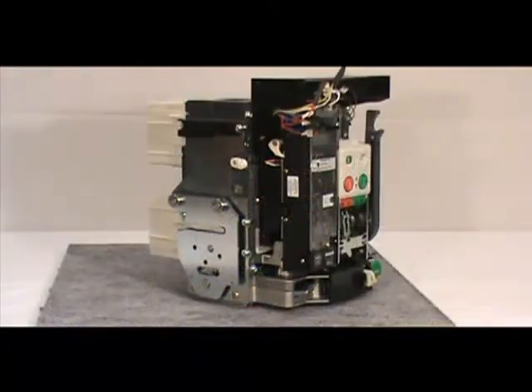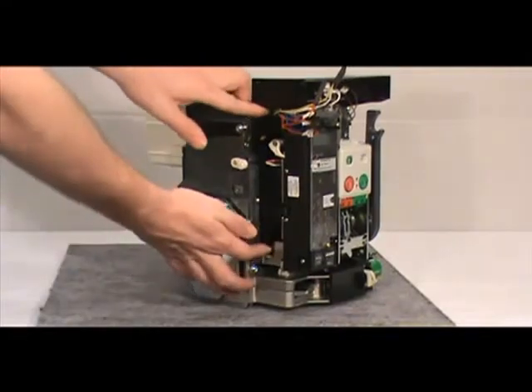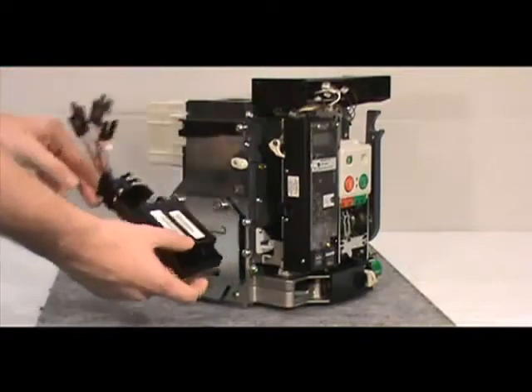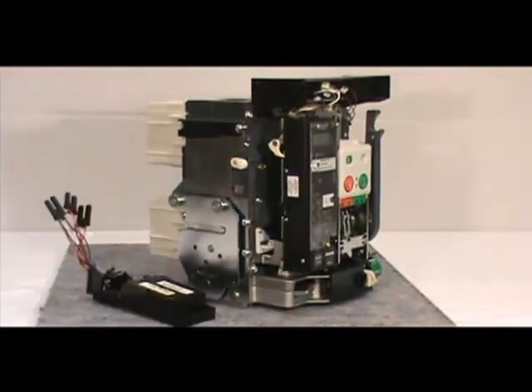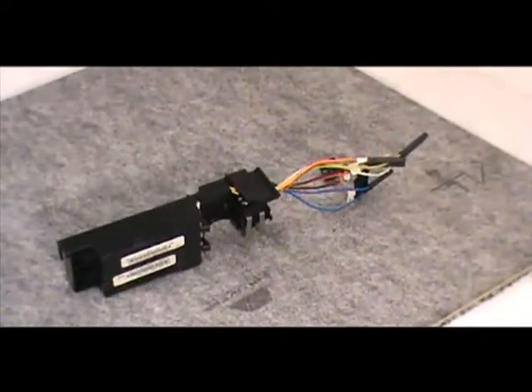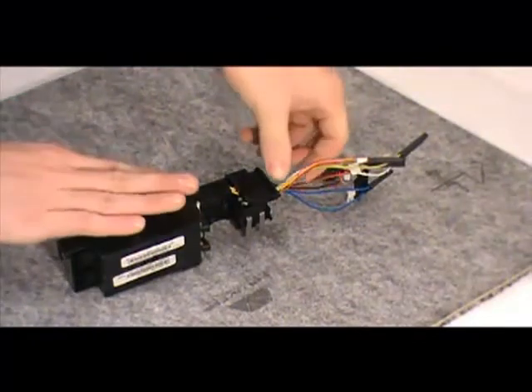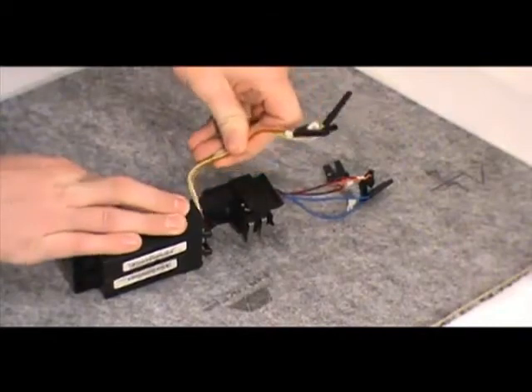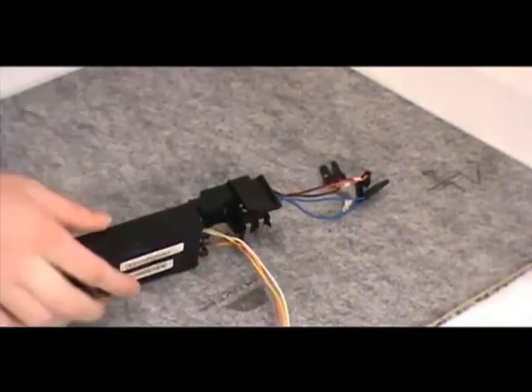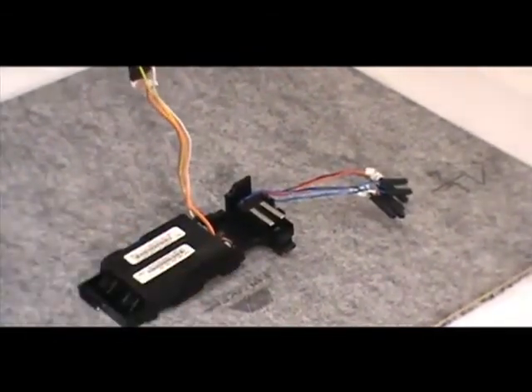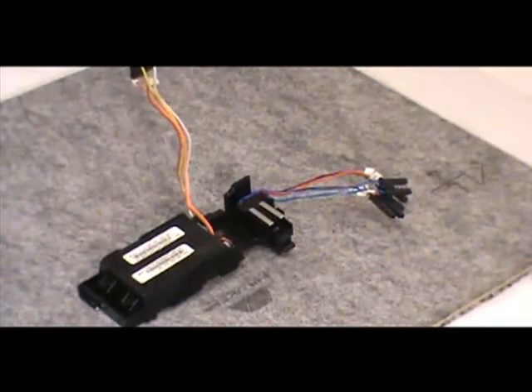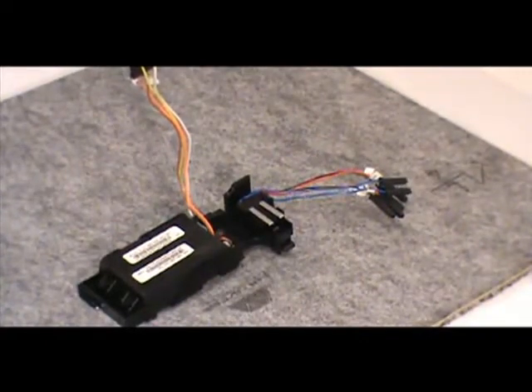Now depress the tabs on each end of the left accessory tray and slide it out. Then remove the lead wires from the molded retaining tabs. First, we'll remove the undervoltage release and the shunt trip. To do so, pull back on the locking tab to unlock the UVR and shunt trip, then lift each accessory upward and out.